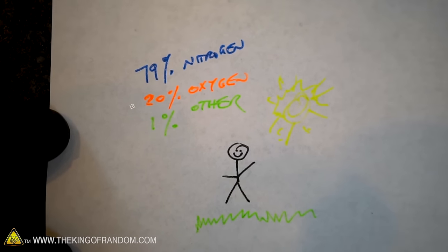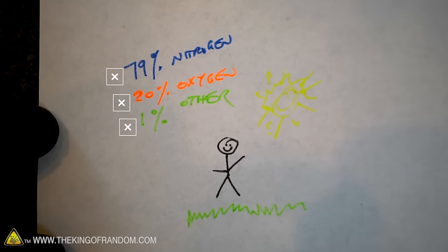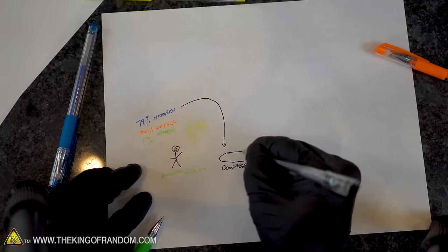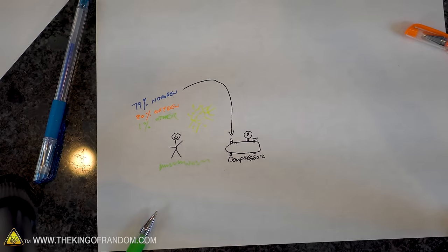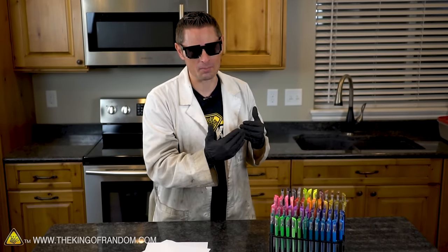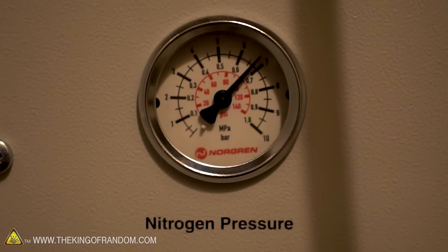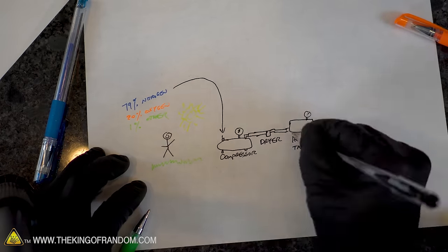Now if you go outside and take a deep breath, you're filling your lungs with about 20% oxygen, 79% nitrogen, and 1% other gases. The first step in making liquid nitrogen is to take the regular atmosphere and compress it into some kind of container that can hold it under pressure. Once it's under pressure, we can pass it through a nitrogen membrane which will separate the oxygen and other gases, leaving pure nitrogen gas behind. But there is one other problem: the nitrogen might have some moisture associated with it, and we don't want any moisture. So the next step is to pass that gas through some kind of mechanism that dries it out.